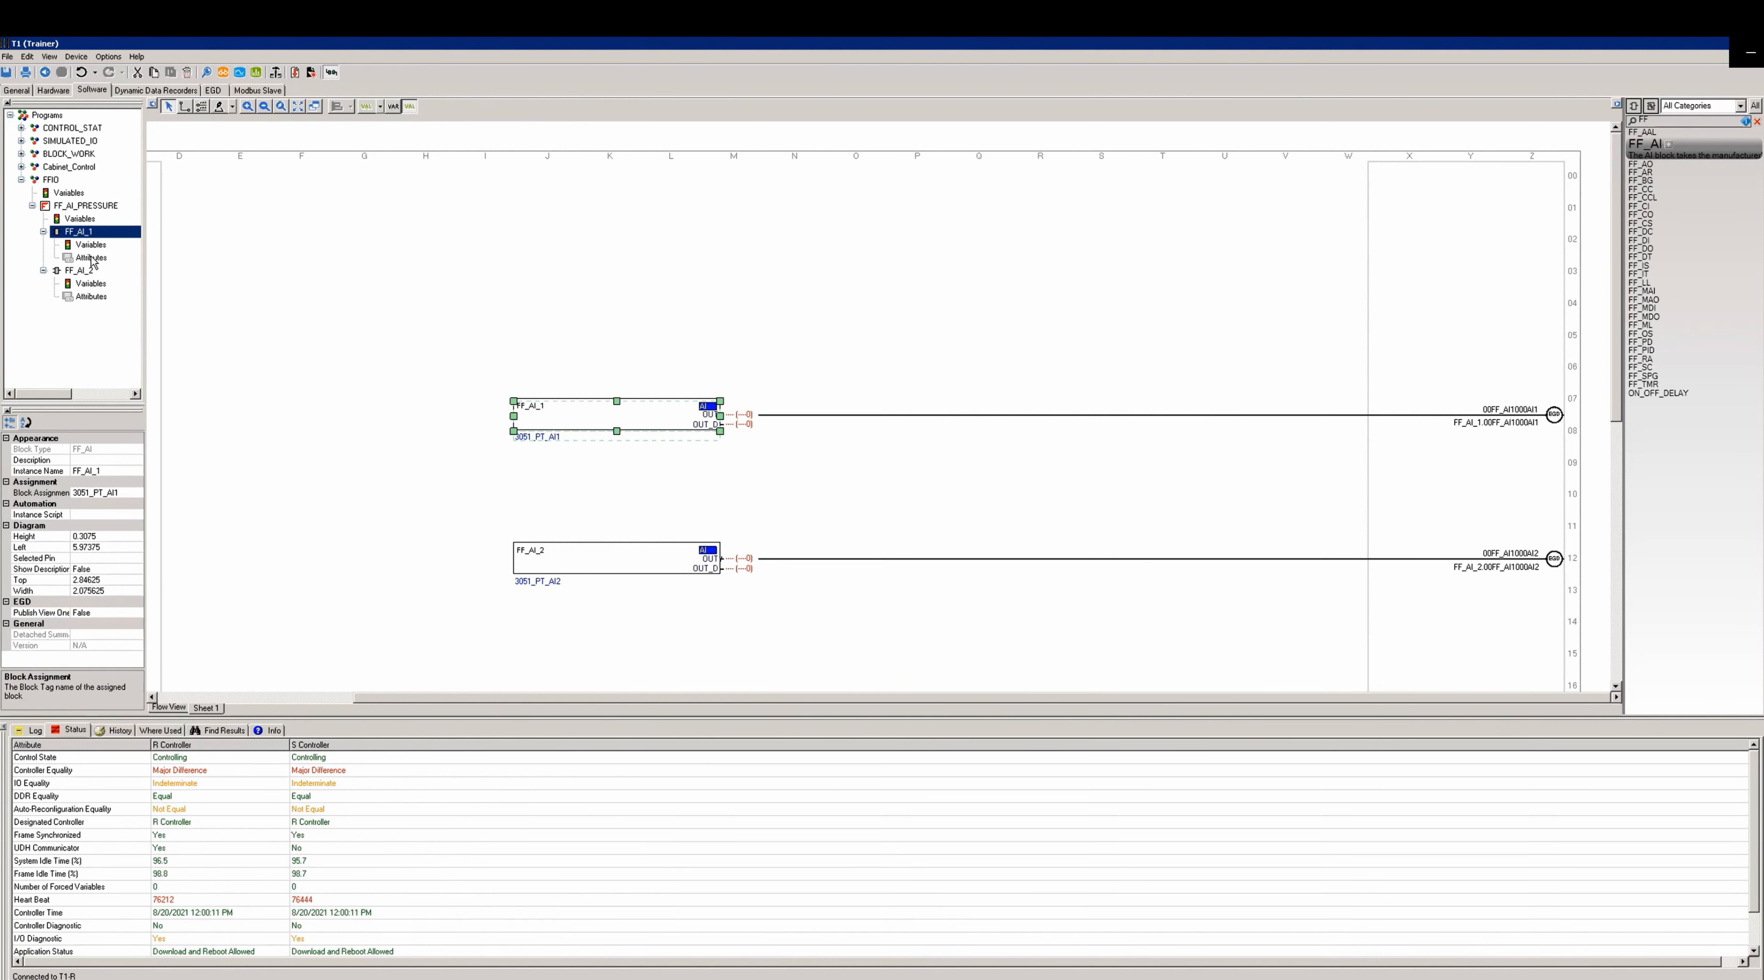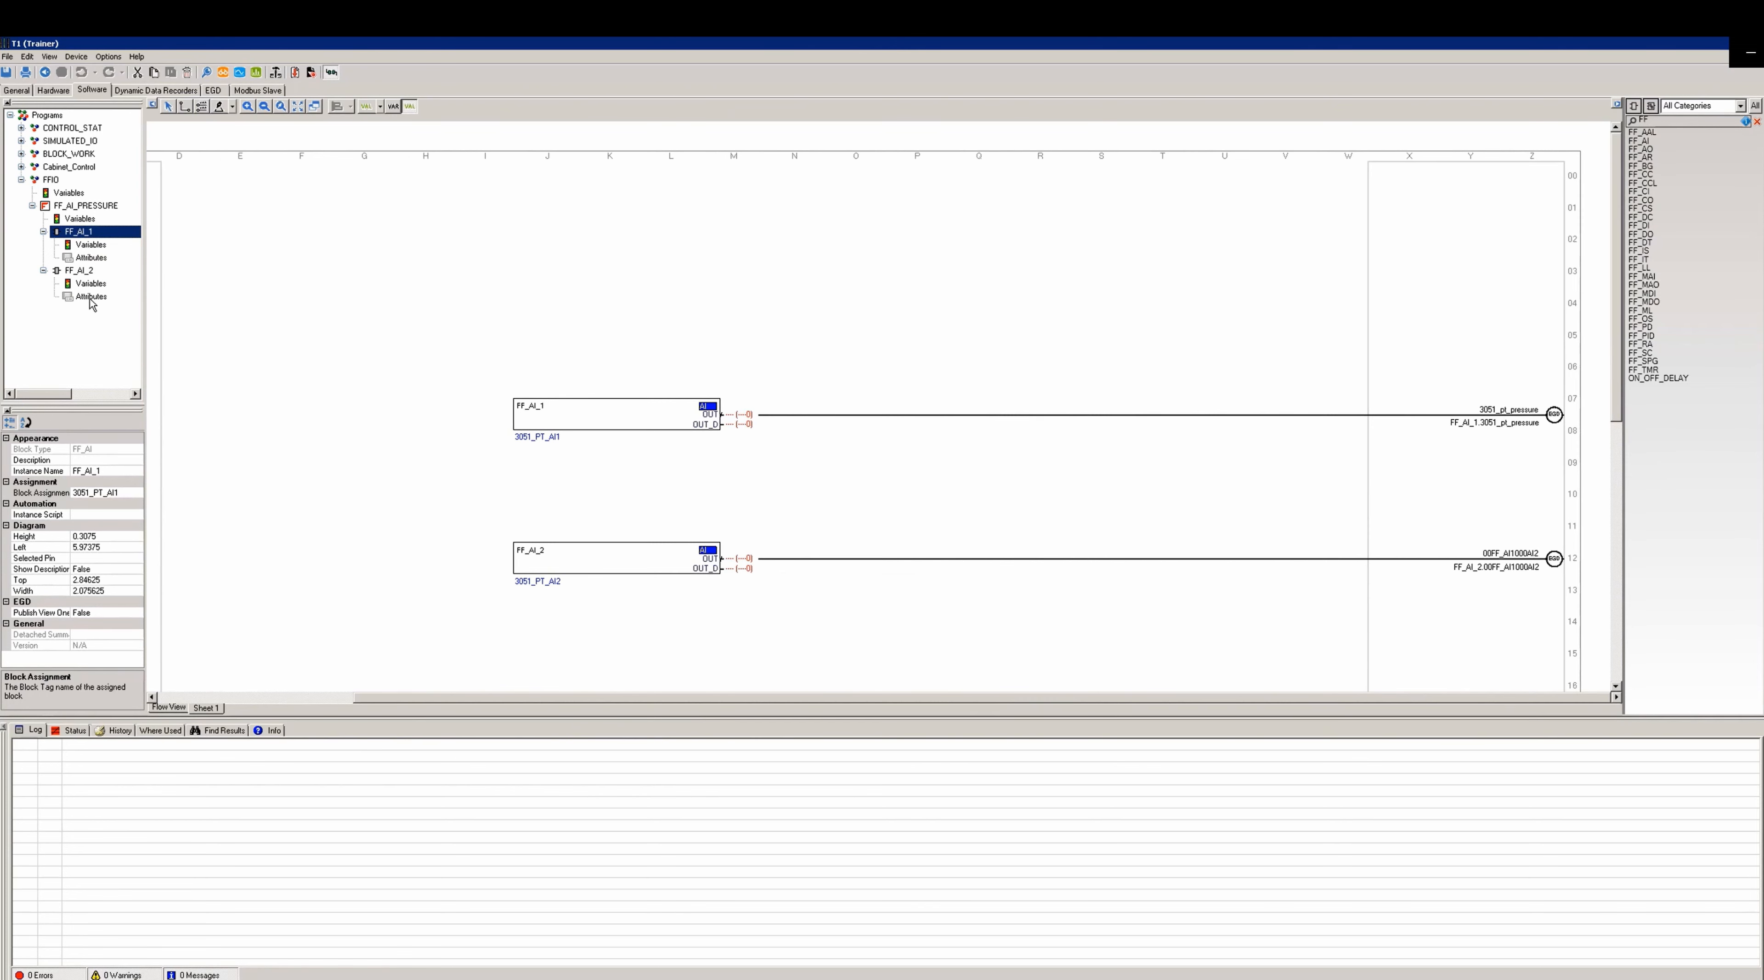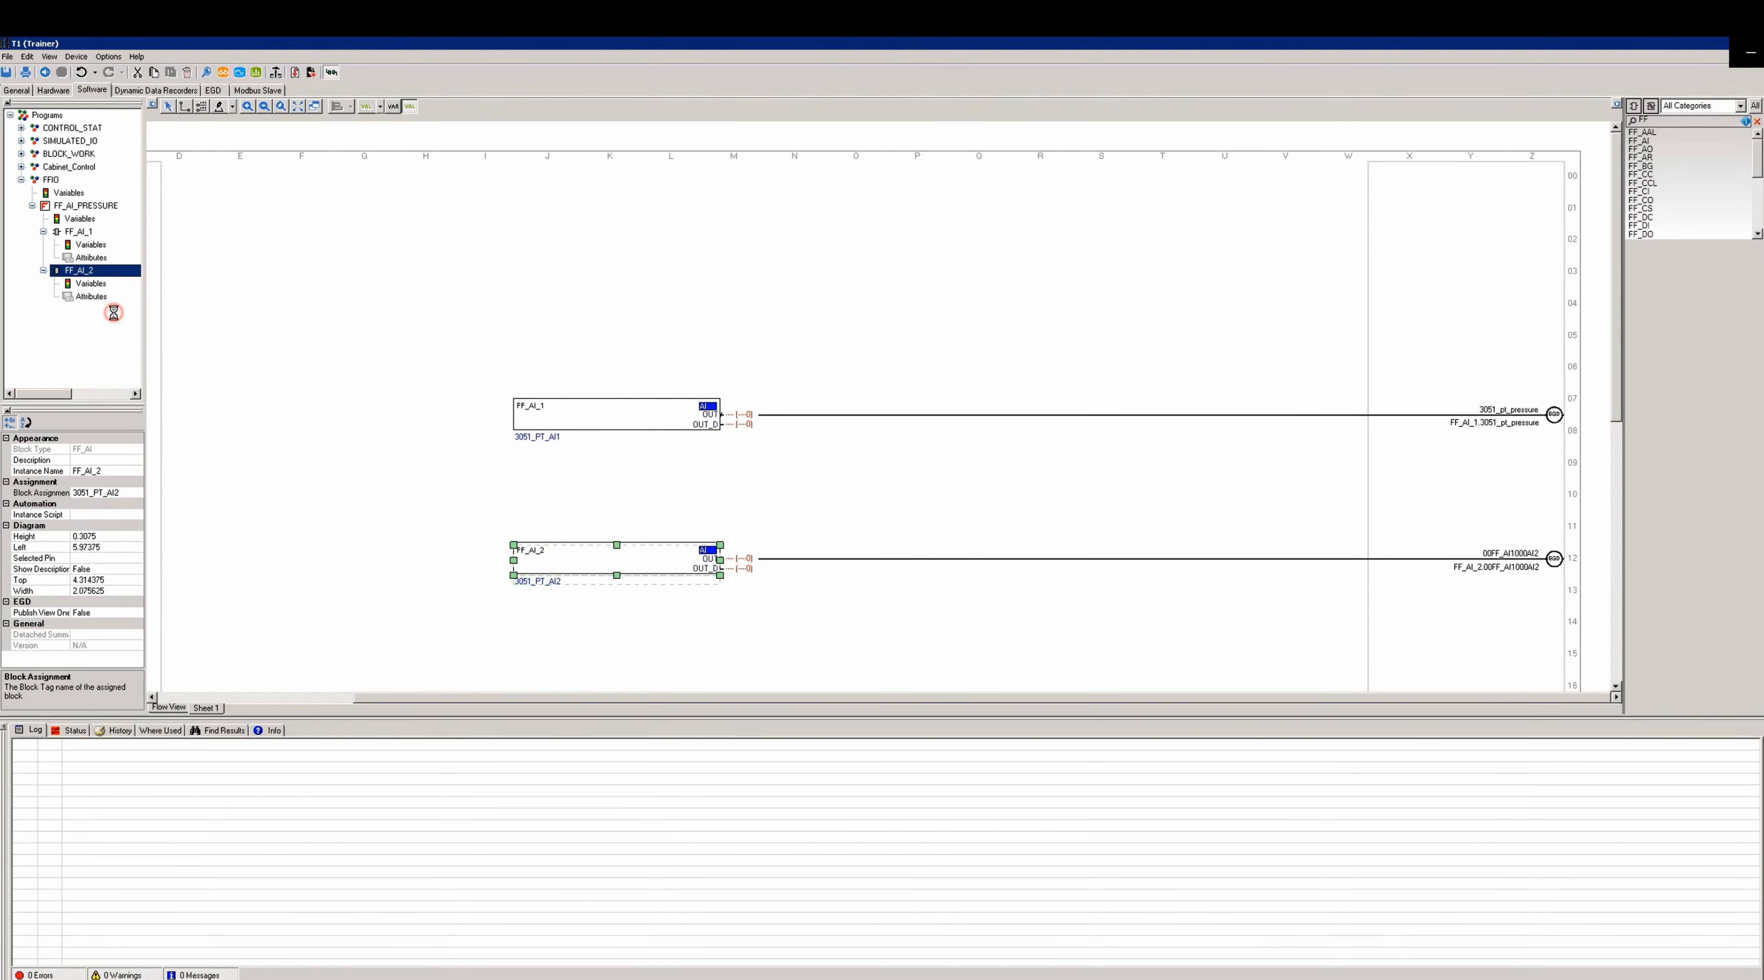After you've added these, if you want to change any details about them, you can go to the attributes for each block and modify the descriptions. The change won't take effect until you right-click and instance the FFAI. This will bring the attributes up to the variables for the device. We'll do the same on the other AI as well. We'll modify the description and change the device tag name. As before, the changes won't take effect until we right-click and instance the attributes up to the variables.